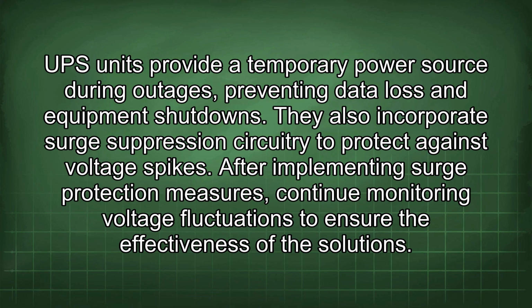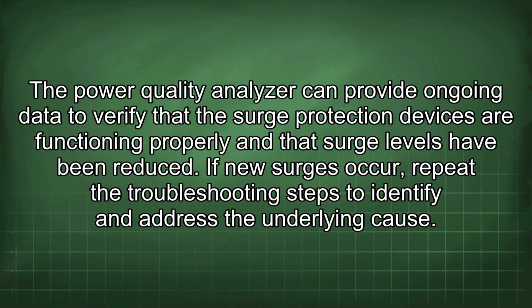After implementing surge protection measures, continue monitoring voltage fluctuations to ensure the effectiveness of the solutions. The power quality analyzer can provide ongoing data to verify that the surge protection devices are functioning properly and that surge levels have been reduced. If new surges occur, repeat the troubleshooting steps to identify and address the underlying cause.